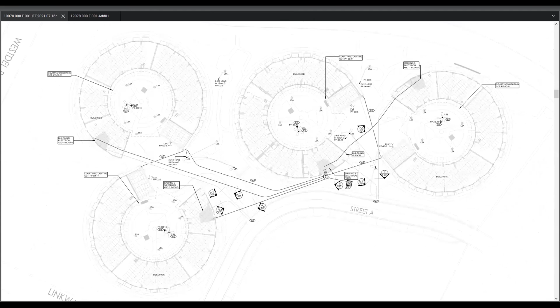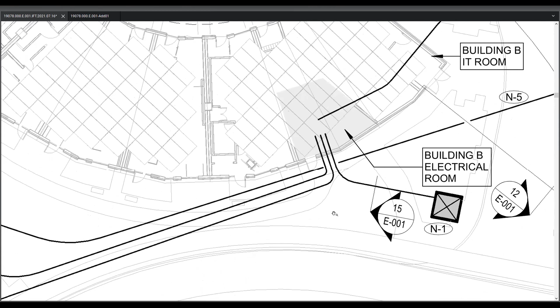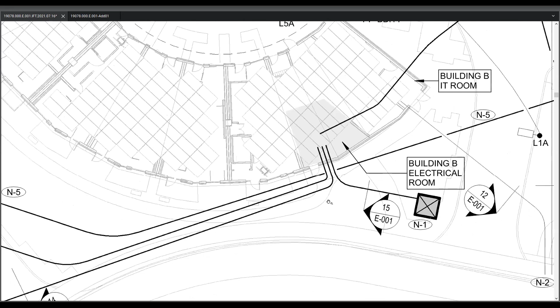This becomes important because in the area out front of building B there'll be a lot of excavation and coordination of duct banks. You'll see in our duct bank schedules that we can't have feeders too close together. They need to be spaced apart so the heat from one feed doesn't affect the ampacity of a separate independent feed. That'll require a good amount of coordination with the construction manager.